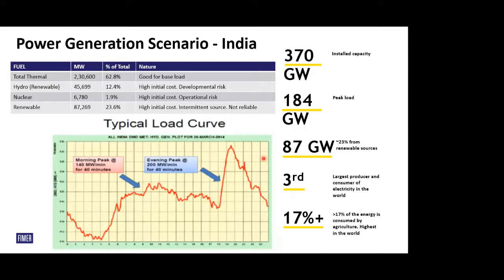Nuclear has a very high initial cost again, but it also poses some operational risk. Renewable is very clean, but it is usually an intermittent source and not very reliable. Even though there are 370 gigawatts of installed capacity, the peak load observed in 2019 was around 184 gigawatts, and it is again year dependent. Usually in the monsoon and harvesting time the load increases, which comes between July and August, and the peak load observed was somewhere close to 184 gigawatts last year.